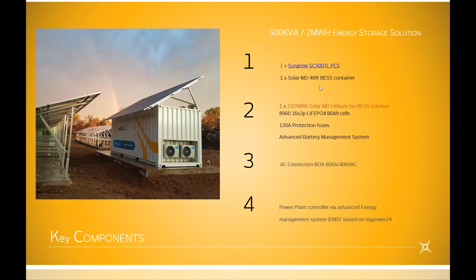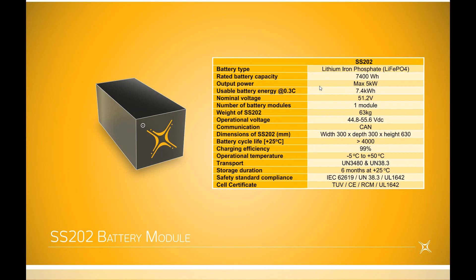So 14 SS202 modules are connected in series, and they build a 712 volt DC voltage. There are DC fuses and contactor protection, then it gets connected to the PCS. The PCS can be inside the container, or also an external device for bigger solutions. Let's say, for a 10 megawatt-hour solution with a 2 megawatt PCS, typically the PCS is in its own container.